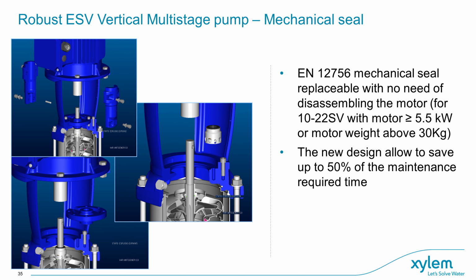On pumps with motors larger than 5.5 kilowatt or heavier than 30 kilograms, the ESV comes fitted with a cartridge mechanical seal as standard. This allows for a single engineer to attend site and replace the mechanical seal safely and quickly, as the motor remains in place and does not need to be lifted from the wet end.